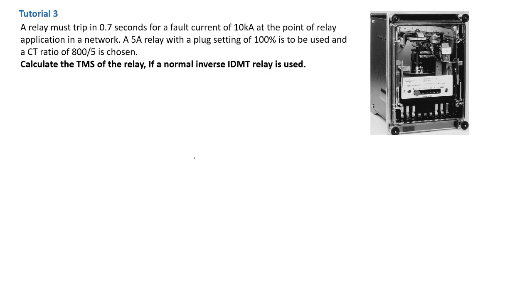Welcome back to Simtech channel, this is Chad from Simtech. This is Tutorial 3 on IDMT relay calculations. In this tutorial, a relay must trip in 0.7 seconds for a fault of 10 kilo-amps, where the fault is located at the point where the relay is on the network. We have a 5-amp relay nominal current, and the plug settings are set at 100 percent.